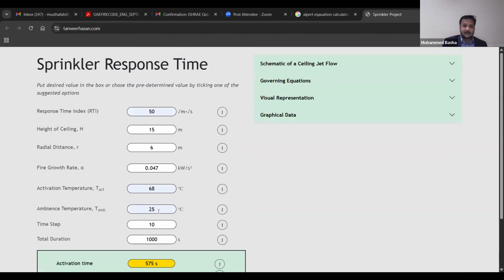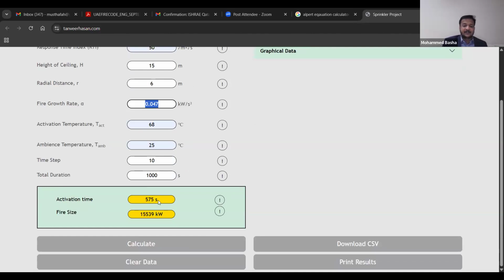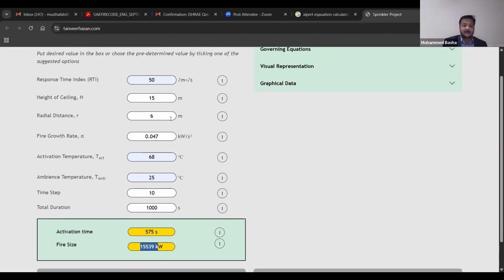If you use Alpert's correlation equation for a fast growing fire, because 0.047 is a fast growing fire, a sprinkler located at 6 meters needs 575 seconds to activate. At 575 seconds, the fire will be 15 megawatt. But if you put the sprinkler closer, I mean, don't put it very far, you change your design, because 15 megawatt seems very high and you would need huge extract fans.